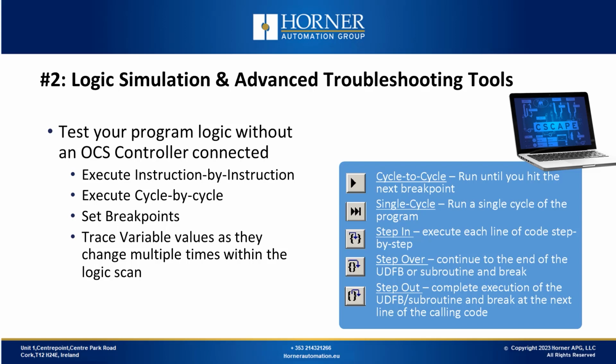There are some handy tools available. For example, you can execute instructions step by step, aiding in troubleshooting. You can run one scan at a time, checking the results at the end of each scan. Setting breakpoints in your logic allows you to examine what occurs up to a certain point when execution pauses. Another useful feature is setting trace points. You can attach a variable to a trace point, allowing you to monitor its value throughout the scan. Regular troubleshooting would only show the value at the scan's end, but with trace points, you can track every value and its timing, which can be exceptionally valuable.